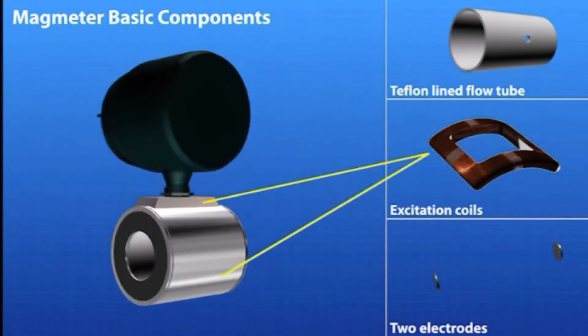Current is applied to the coils in the magmeter to generate a magnetic field within the flow tube. As a conductive fluid flows through the meter, an electromotive force is generated. This force is detected by the electrodes, and the resulting value is converted to flow rate.